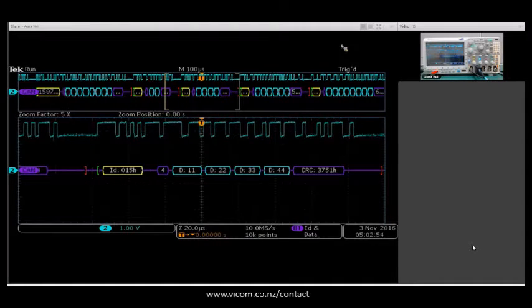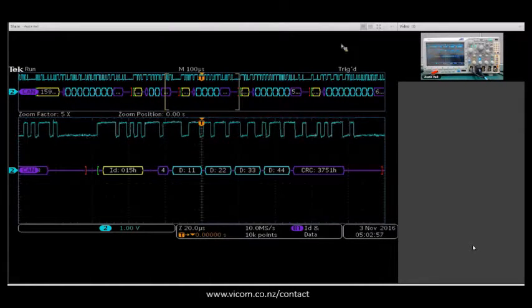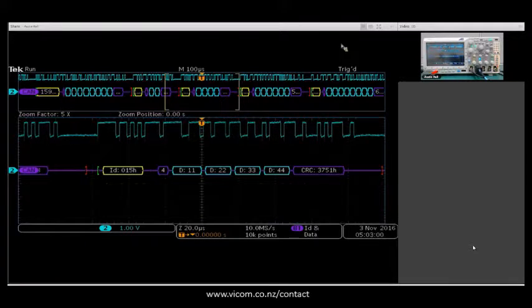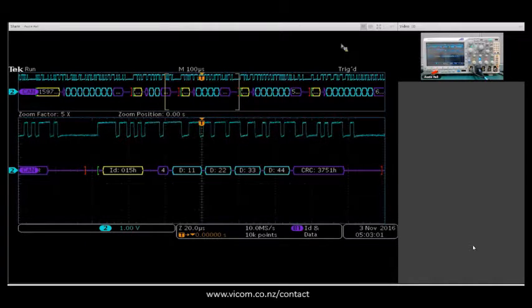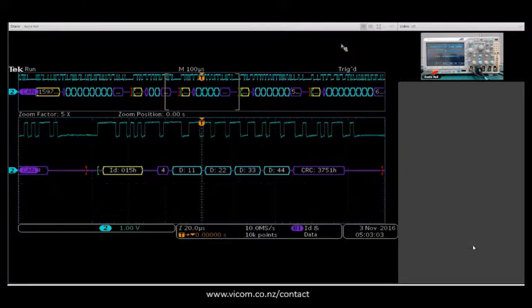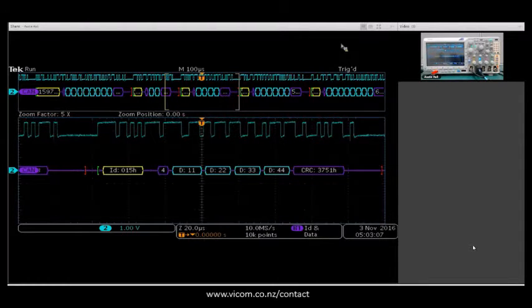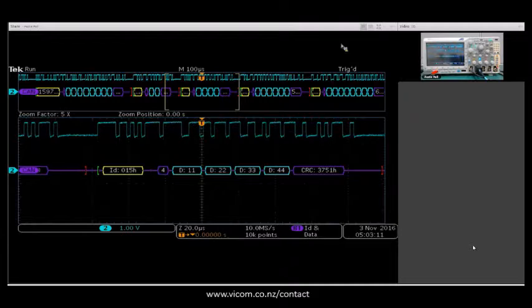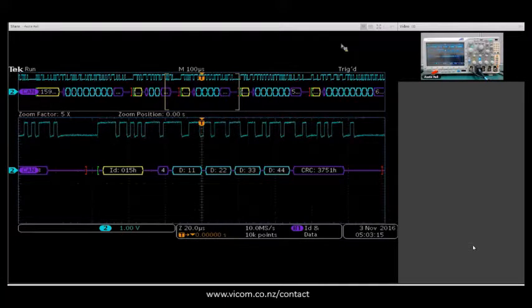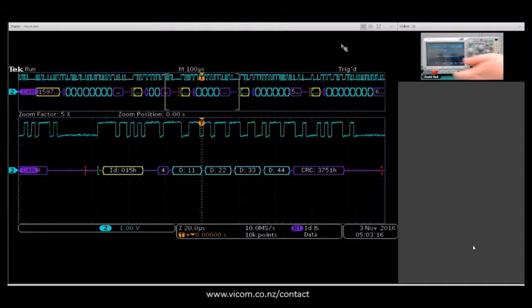I'd like to take a moment to show you the CAN decode available on the MDO 3000 here. What we have here is a CAN bus signal coming in. It's specifically CAN-high. We are doing a packet decode on that. What I can show you here is how to set that up from a default setup.